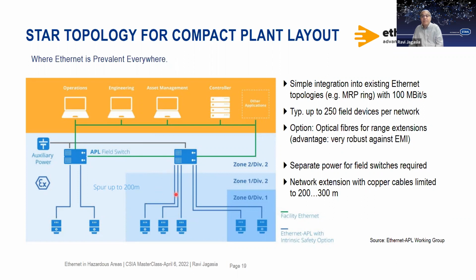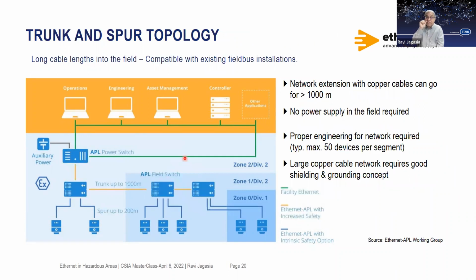The spur length can be 200 meters, and then the extension of the network with the copper cables is approximately 200 to 300 meters. You cannot do more with this, and this would be a very good application when the plant layout is compact. You would definitely feed an auxiliary power to these devices because they are not sourcing their power from anywhere else. Going further into a bigger structure, you would have a power switch.